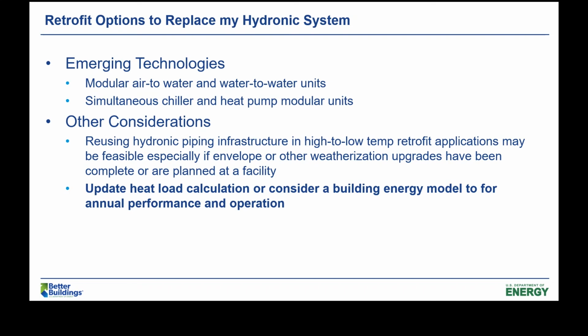In the space of hydronic heating systems, there are some emerging technologies worth pointing out. There are a lot of modular heat pump options available today - small package units you can pair side by side to serve your heating load, rather than buying one big boiler or two for redundancy. These modular pieces allow you to pair multiple same-size units together, which serves a lot of purposes: they can be staged to improve performance, and it allows considerations around defrost cycles, where you can have a redundant unit or one unit always in defrost.